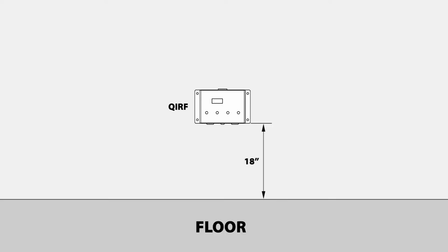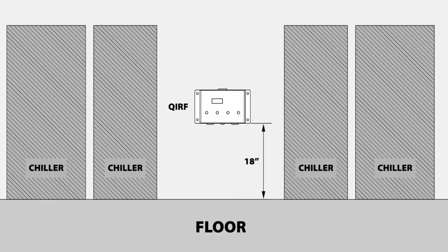A couple things to keep in mind when installing QIRF refrigerant sensors. Since Freon is heavier than air, the QIRF should be mounted 18 inches off the floor or in any low areas such as pits or stairwells where the Freon might pool. If your application includes multiple chillers, mount the QIRF between the chillers.